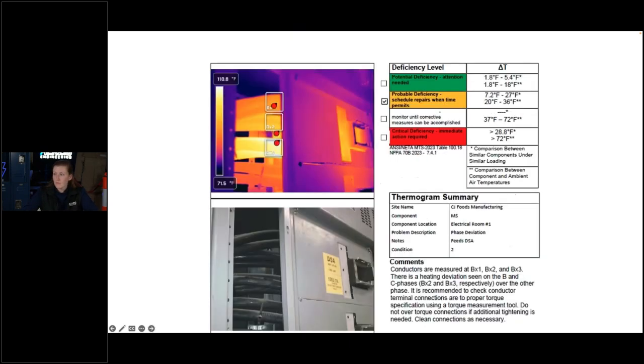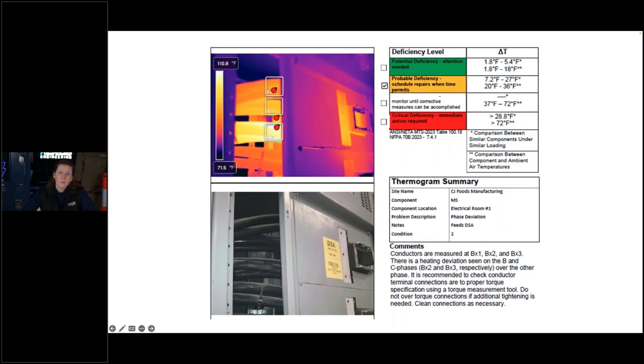Here's another one that's a probable deficiency. One of the phases is quite a bit warmer than the other two, a problem we see often, typically associated with a loose connection, possibly some unbalanced loads, but most of the time it's from a loose connection, at least generally speaking.